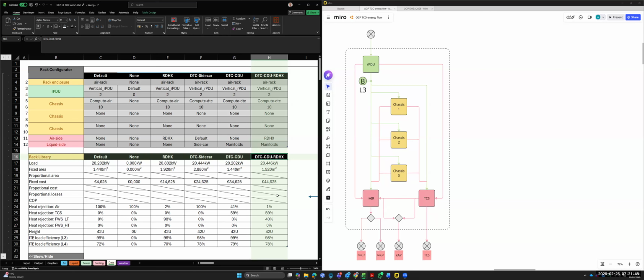So in this case, you can see that accounts for the combination of the overhead power for the CDU and the rear door heat exchanger. It also accounts for the capital cost of all that extra equipment and the floor area. As you'd expect, the heat is rejected mostly to the TCS heat rejection pathway.